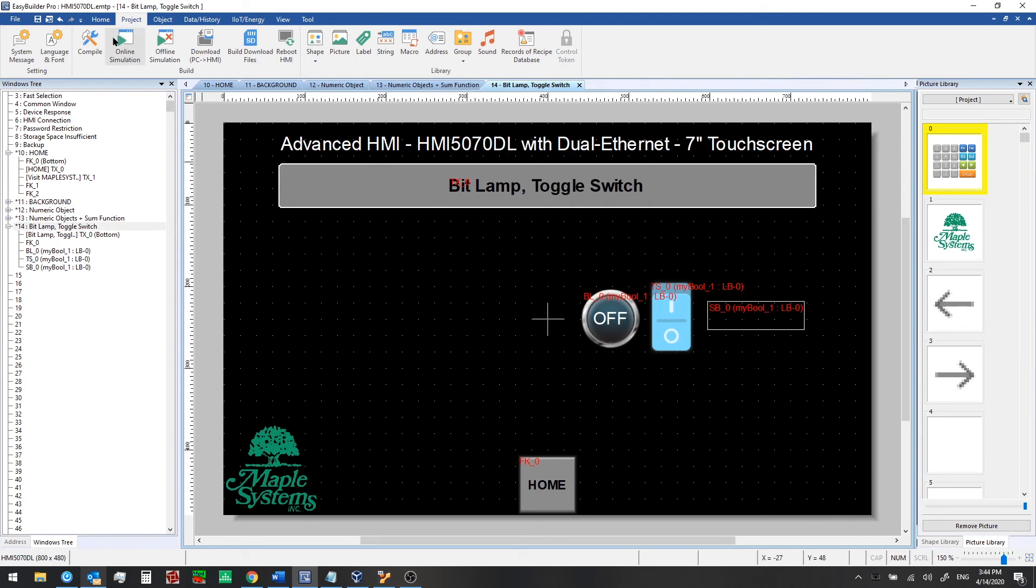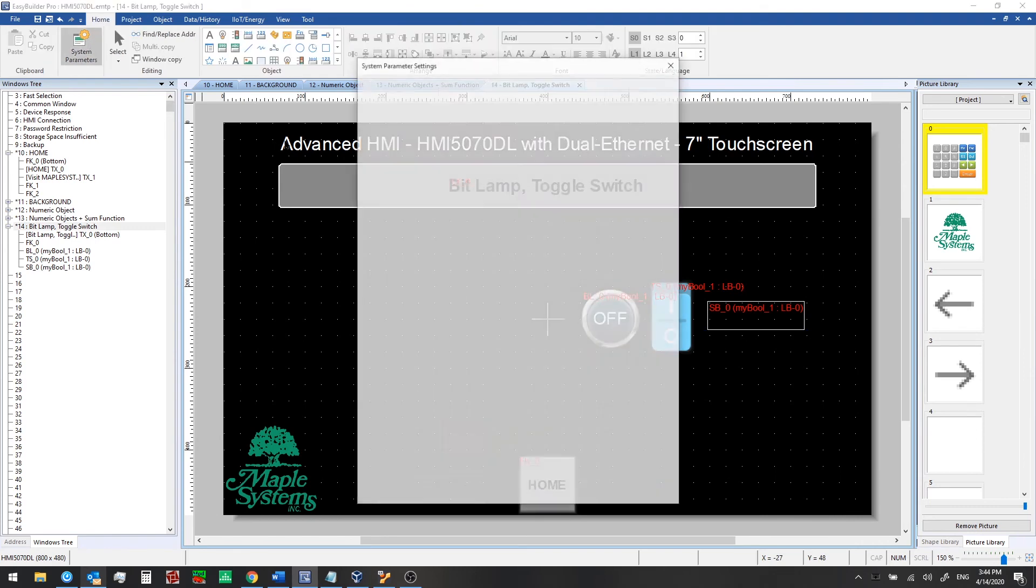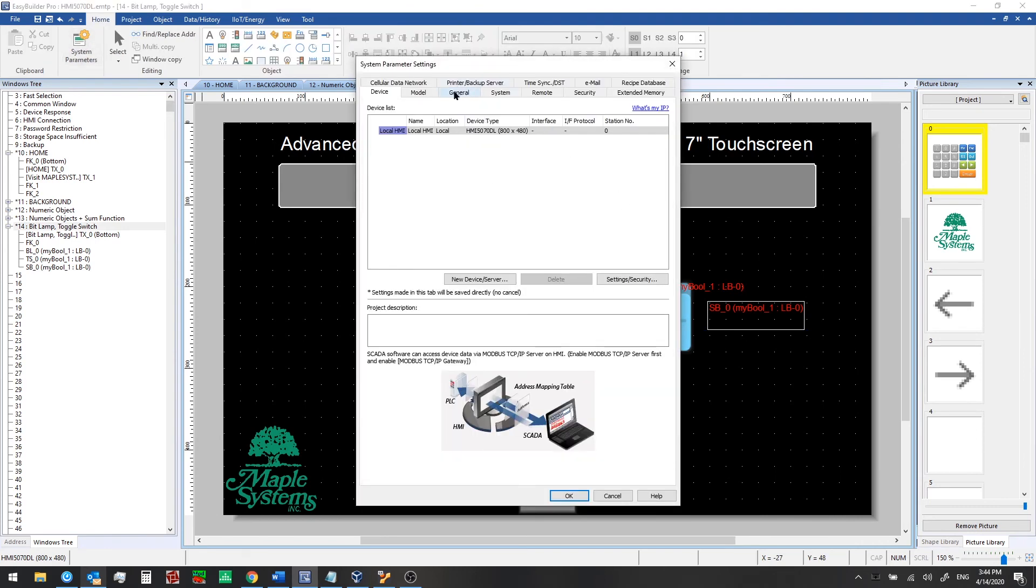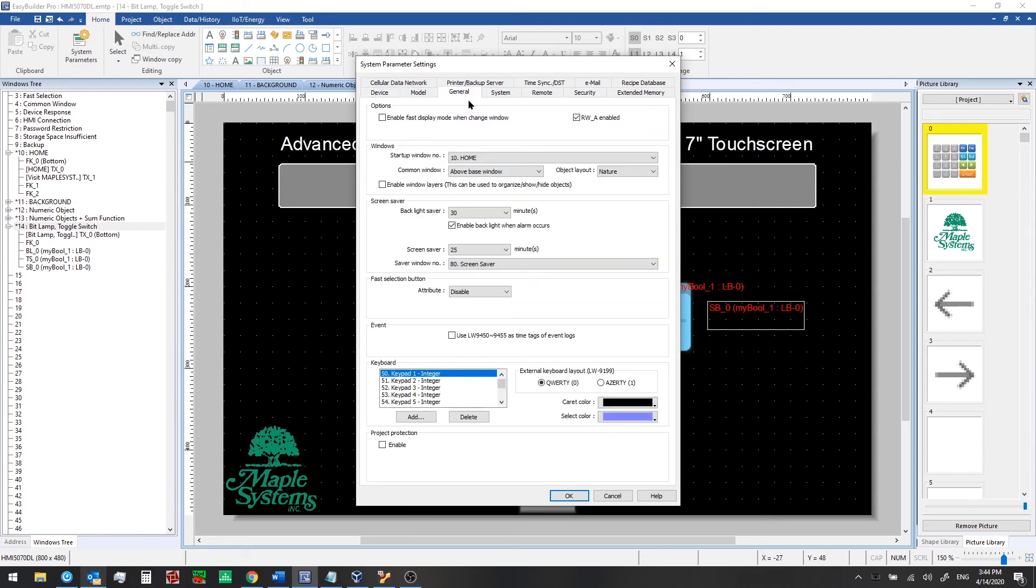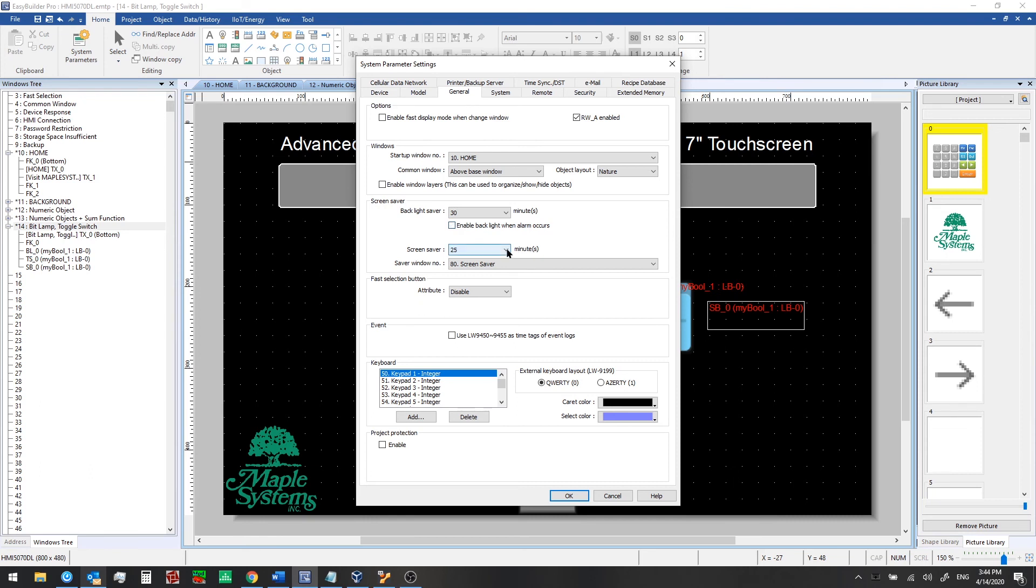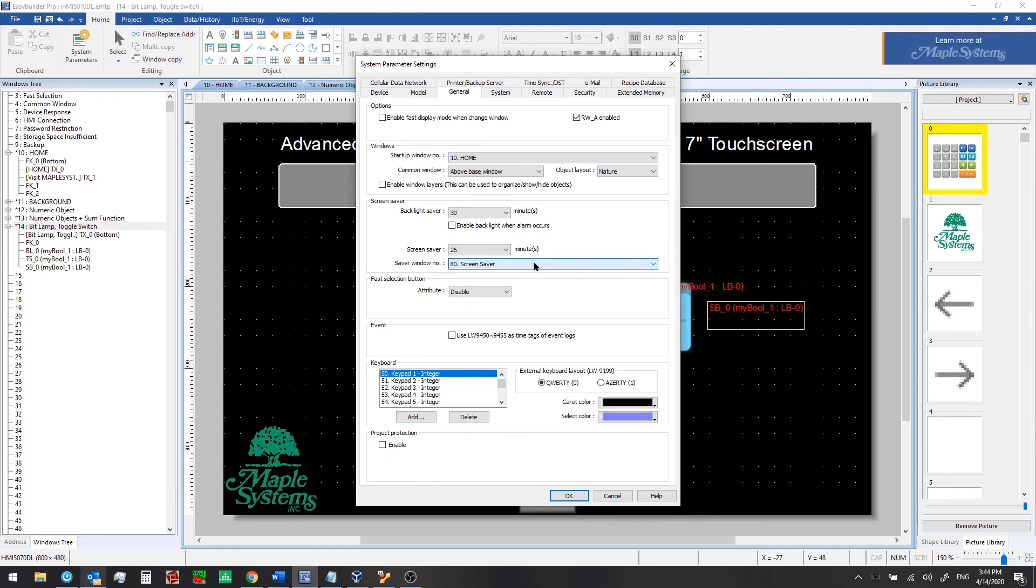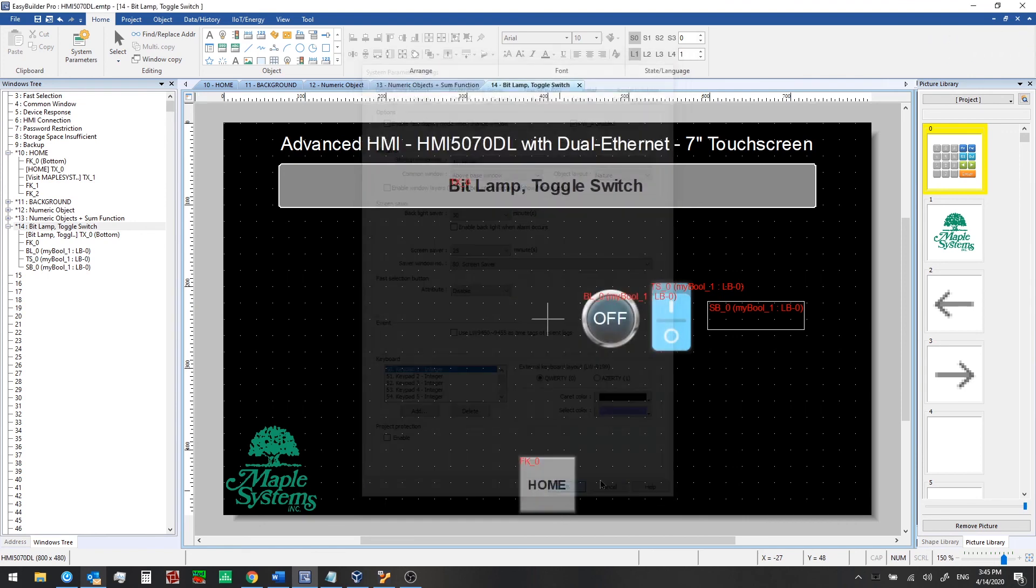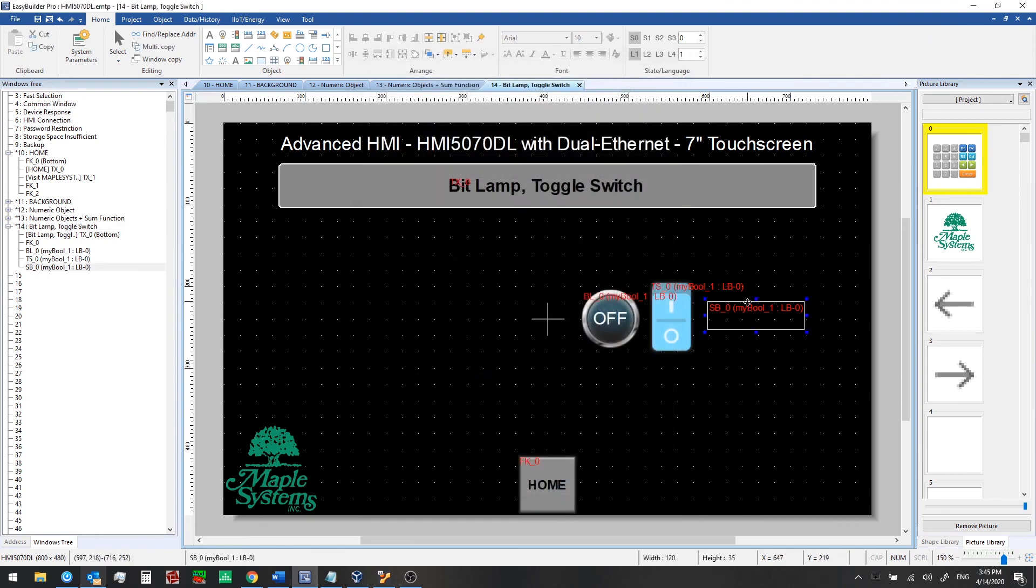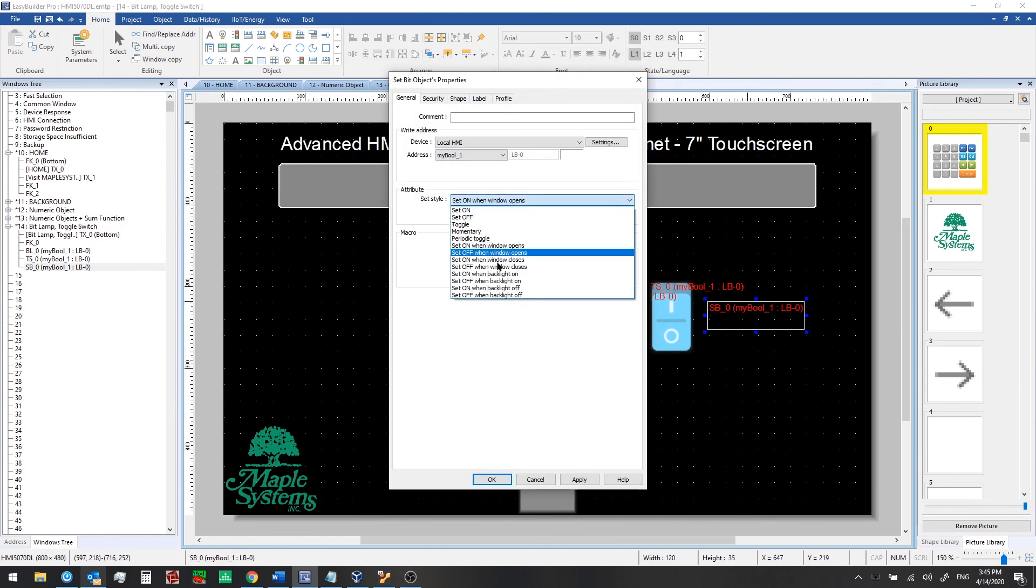Just note where the sleep settings are here. If you go to system parameters in the home tab, click on the general tab here. And we have this under the screen saver section. So backlight saver. By default after 30 minutes it's going to turn off the display. And then if any alarm goes off, the backlight will come back on. So the screen will turn back on. You have that option. You can disable that if you want to. We also have a screen saver that will come on after 25 minutes and it will show the screen saver window which is built in. You can change this. You can modify that window too if you want to. But just note that that's the default behavior. So screen saver shows after 25 minutes, display turns off after 30 minutes. And so you might use that in conjunction with a set bit and these backlight options here.